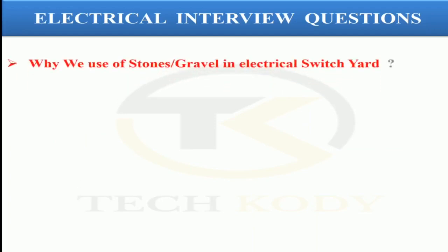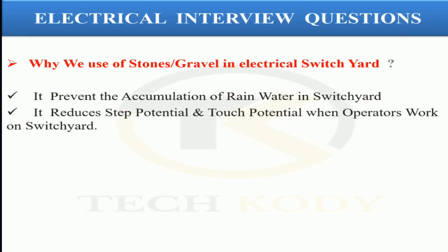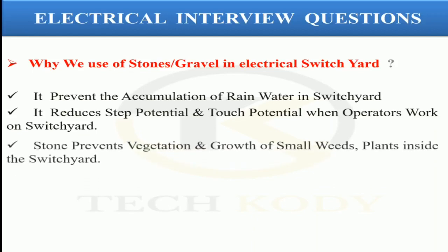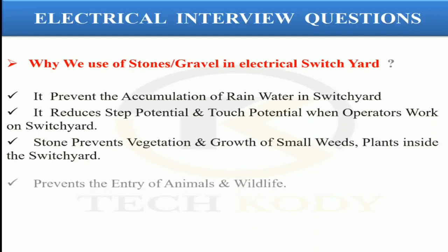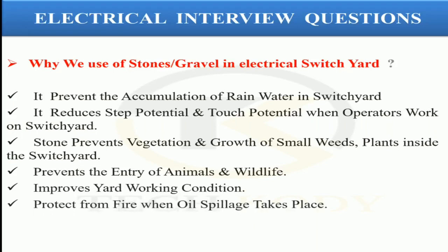The next question is: why do we use stones or gravel in an electrical switchyard? The gravel prevents the accumulation of rainwater in the switchyard. It reduces the step potential and touch potential when operating in the switchyard. It prevents the growth of small weeds and plants inside the switchyard, and prevents the entry of wild animals. It improves the yard working condition, protects from fire when oil spillage occurs, and the gravel increases the resistance between the operator and the ground.